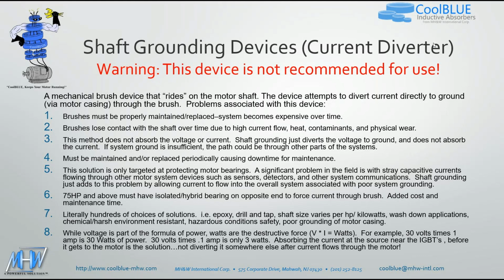A 75 horsepower and above motor must have isolated hybrid bearings on the opposite end to force the current through the brush. Added cost and maintenance time is a result for these larger motors. Number 7, literally hundreds of choices of solutions with the shaft grounding devices. That is, you have to epoxy, drill, and tap. Shaft size varies per horsepower or kilowatts.